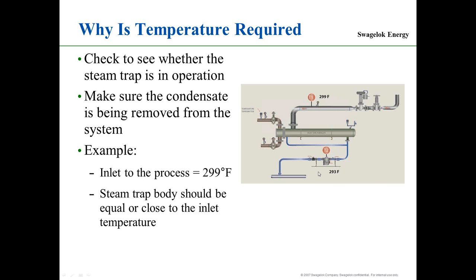The steam trap temperature should be what? Close to 299. Because when steam gives up its latent energy, it changes state from a vapor to a liquid, and there is no temperature change. Now, in the discussion, is there a pressure drop through the heat exchanger?